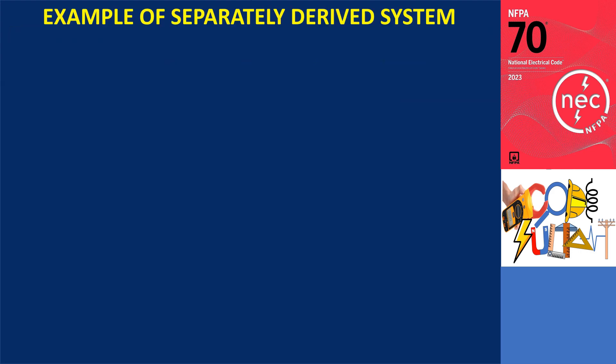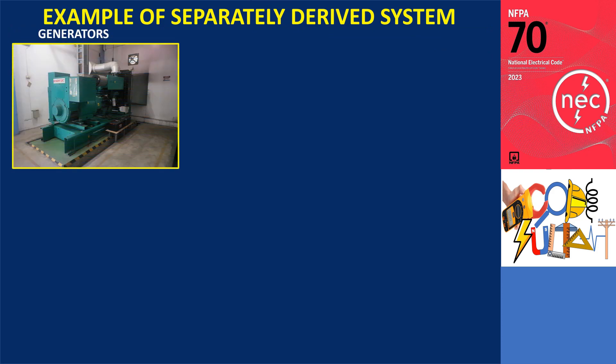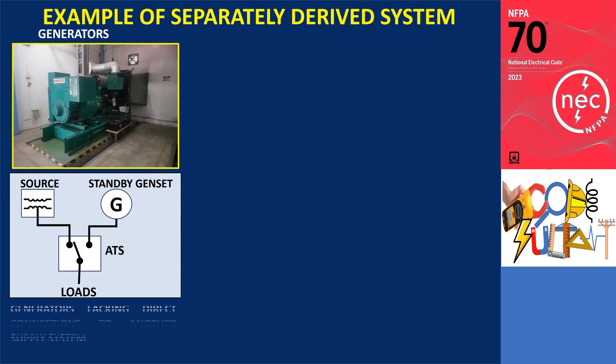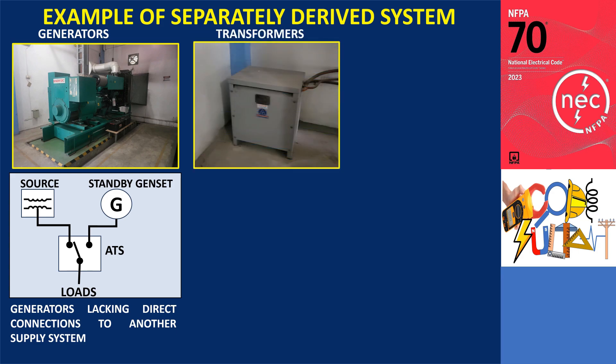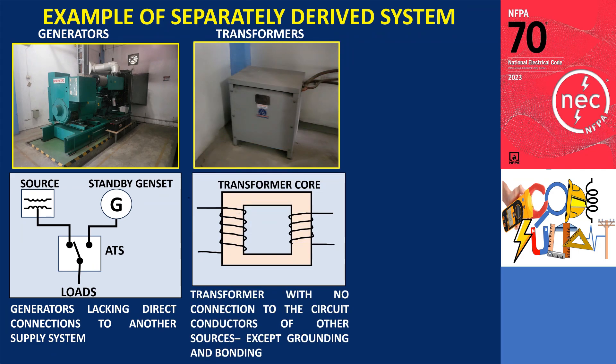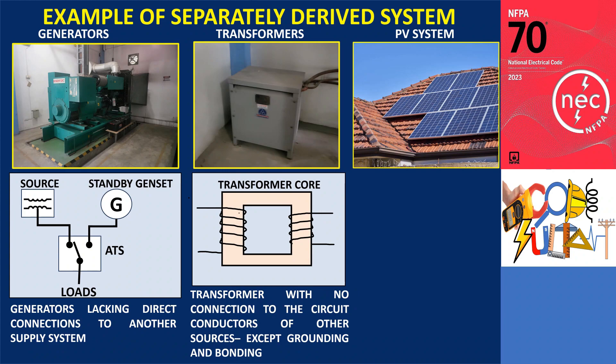Here are a few instances of such systems. This includes standby or emergency generators where the neutral isn't linked to the utility or any other source. Also included are transformers where the primary and secondary windings are electrically isolated but magnetically linked through a common core, resulting in no direct connection between them except for grounding and bonding connections.